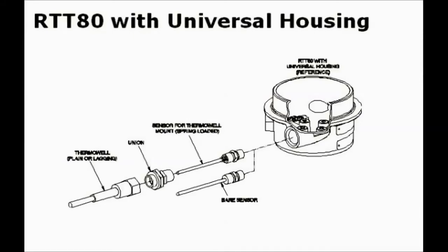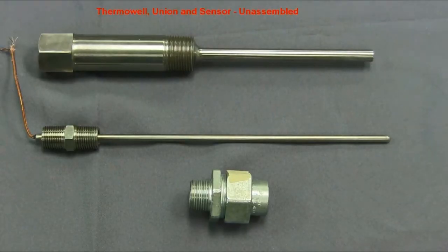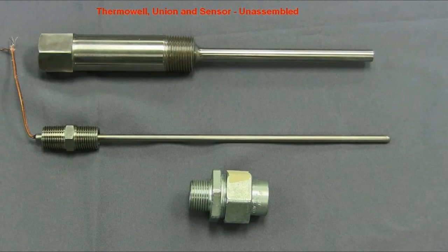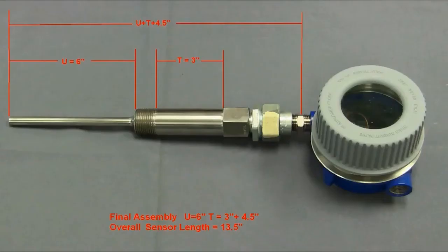Finally, by reassembling the thermowell mounted transmitter, you can clearly see how the components go together with the thermowell and sensor fitting correctly. Looking at the completely assembled transmitter, we see that the sensor length is equal to the thermowell U plus T length and how the factory determined the 13.5 inch overall length.